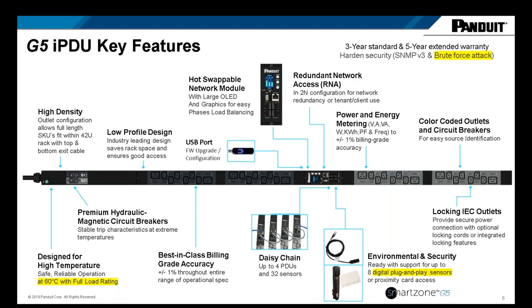That way you could deploy it every 3 cabinets and meet ASHRAE requirements. You can daisy chain up to 4 PDUs and up to 32 sensors, so if you log into a single PDU, you could see all of them on a single IP address.